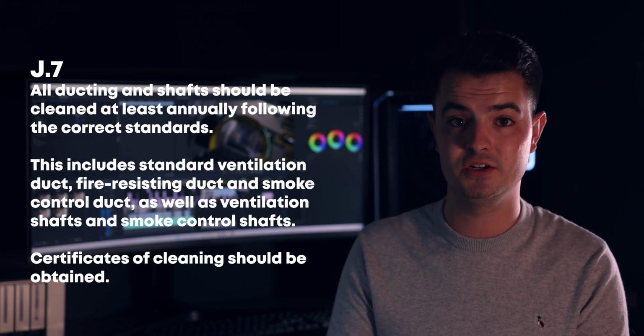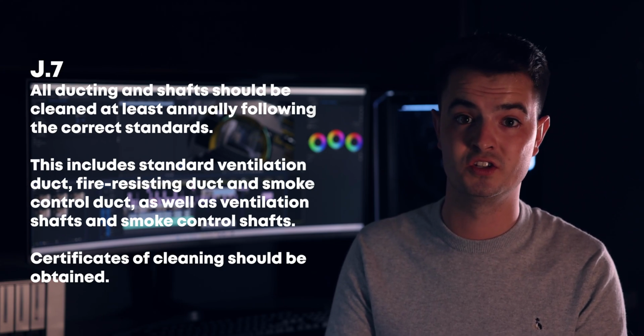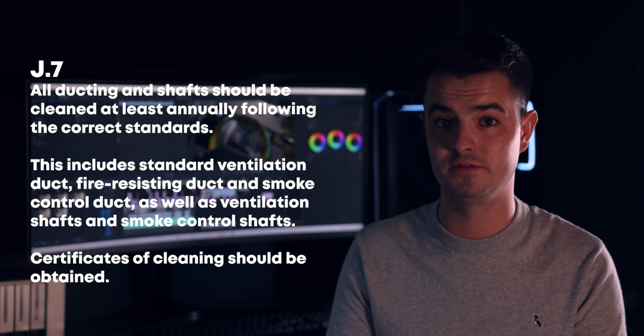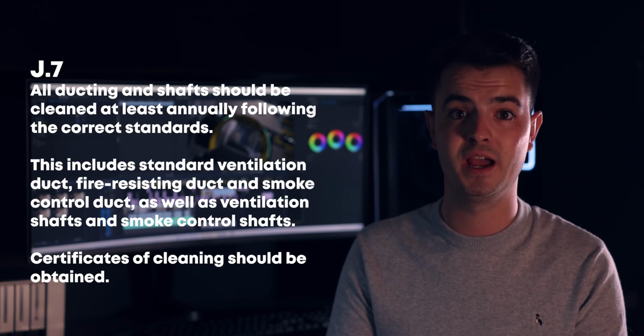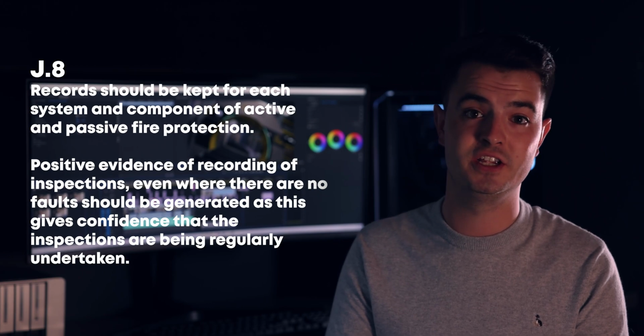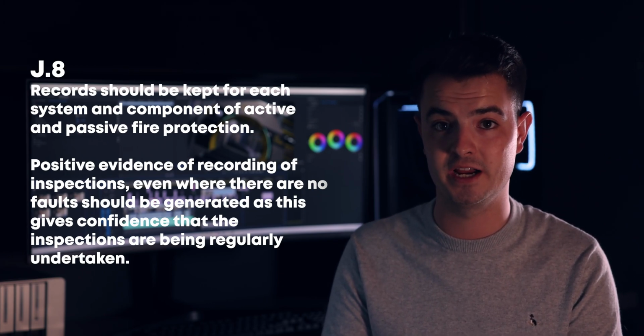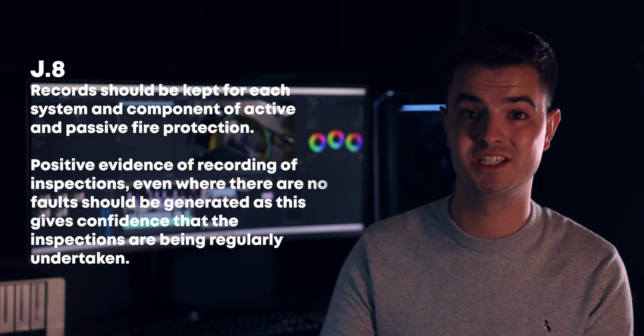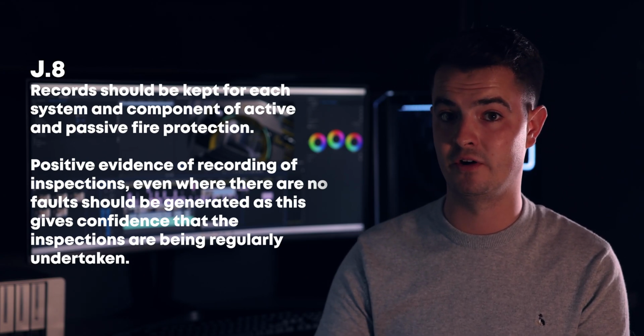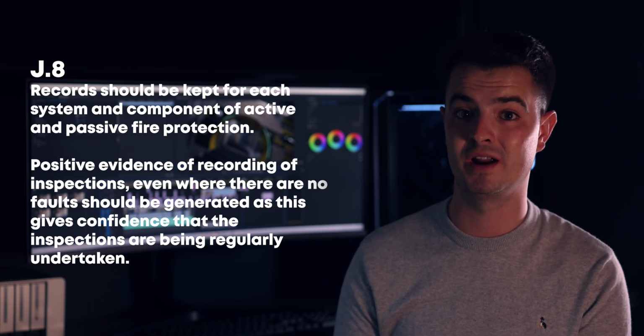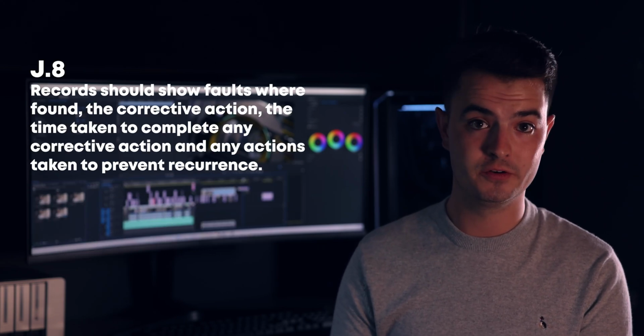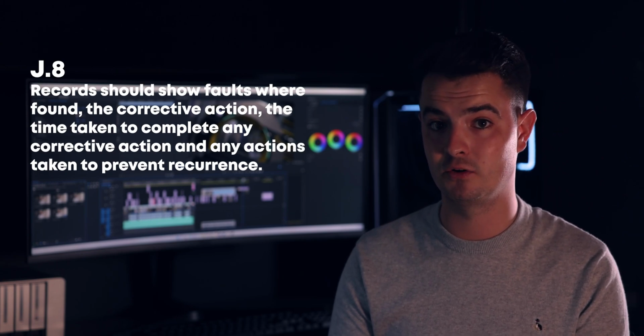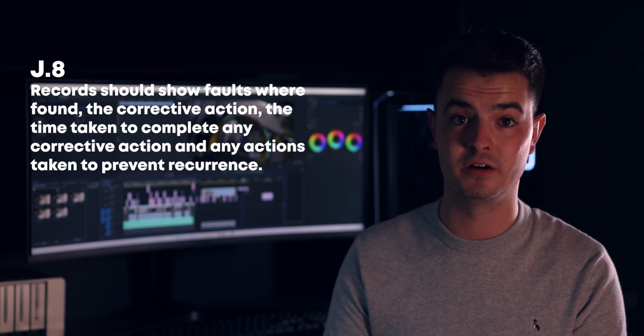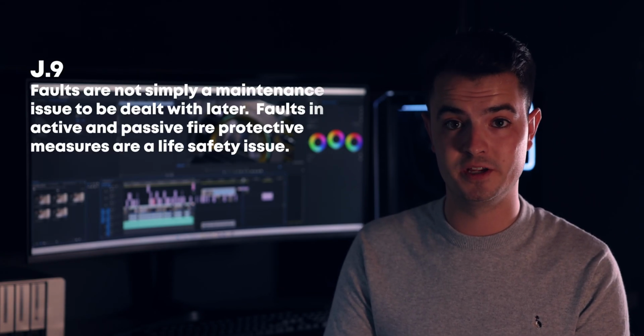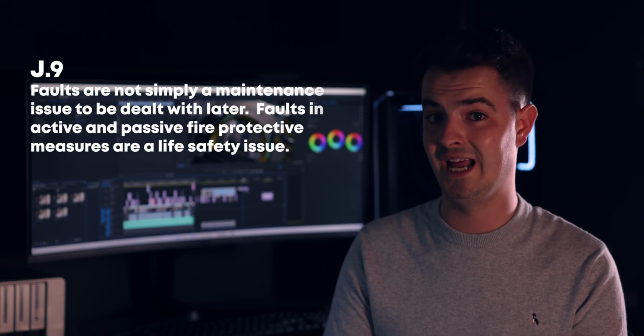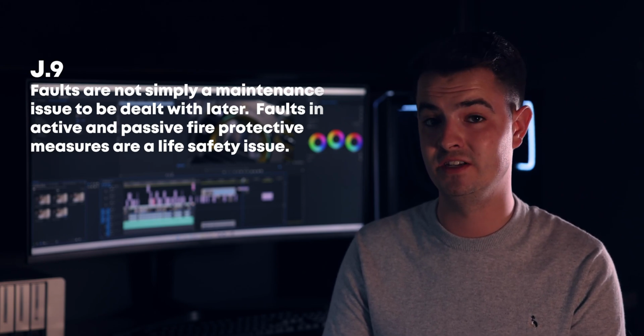This includes standard ventilation duct, fire resisting duct and smoke control duct, as well as ventilation shafts and smoke control shafts. Certificates of cleaning should be obtained. J.8, records should be kept for each system and component of active and passive fire protection. Positive evidence of recording of inspections, even where there have been no faults, should be generated, as this gives confidence that the inspections are being regularly undertaken. Records should show faults where found, the corrective action, the time taken to complete any corrective action, and any actions taken to prevent reoccurrence. J.9. Faults are not simply a maintenance issue to be dealt with later. Faults in active and passive fire protection measures are a life safety issue.